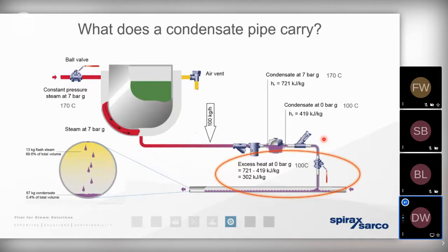But what you may recall from that slide towards the start of today's presentation was that pressure volume relationship. Flash steam that exists at 0-bar gauge is going to occupy a volume of approximately 1.673 cubic meters. In other words, we need to size the pipework downstream of the steam trap to allow for that huge and rapid expansion very, very quickly. And that can be quite costly to do because we could be bringing that condensate infrastructure a considerable run back to the boiler house. So inevitably, at some point, that flash steam will find its way being vented away to atmosphere to allow the condensate to fall back to a single phase liquid again.